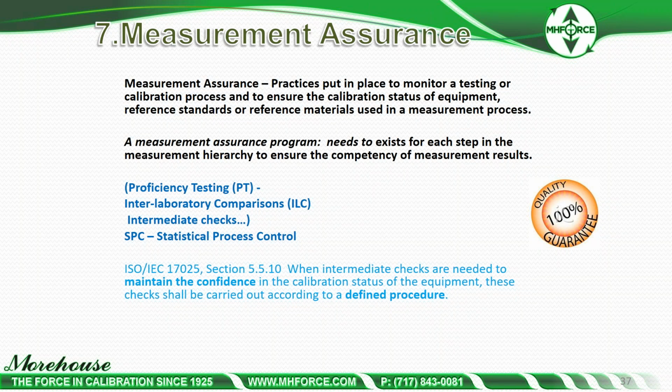document what you're doing. So if we go to section 5.5.10, that specifically states that when intermediate checks are needed to maintain the confidence in the calibration status of the equipment, these checks shall be carried out in accordance with a defined procedure. Well, SPC is a defined procedure. You can write an SPC procedure, and that is a defined procedure.